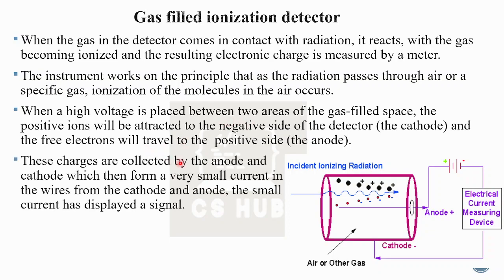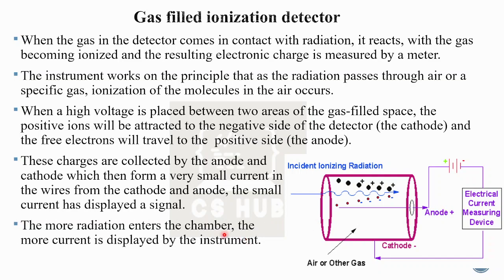These charges are collected by the anode and cathode, which then form a very small current in the wires. This small current is displayed as a signal. The more radiation enters the chamber, the more current is displayed by the instrument. This is the ionization chamber.